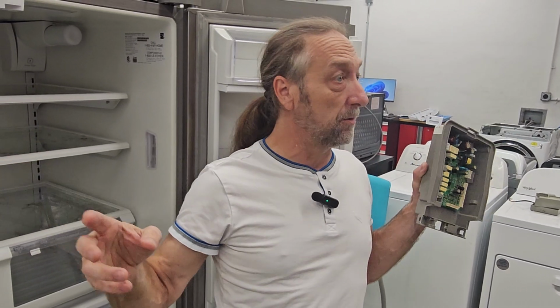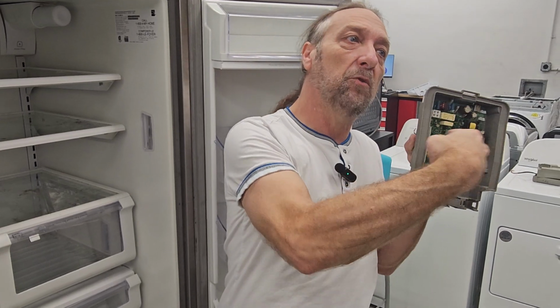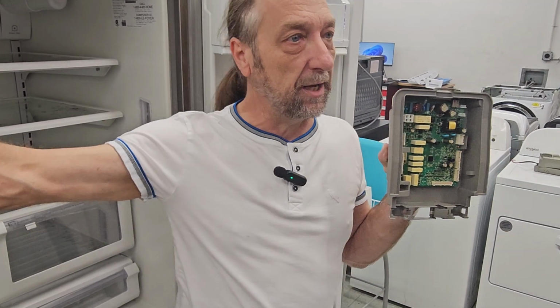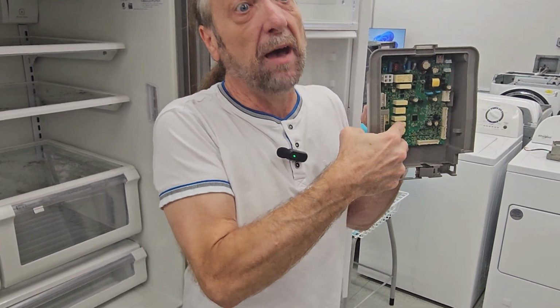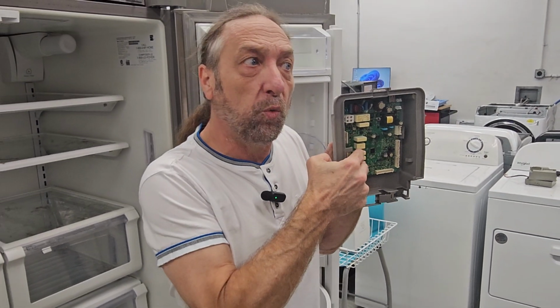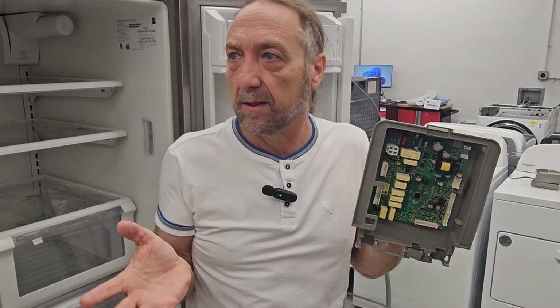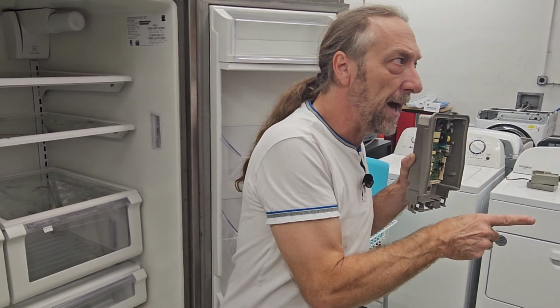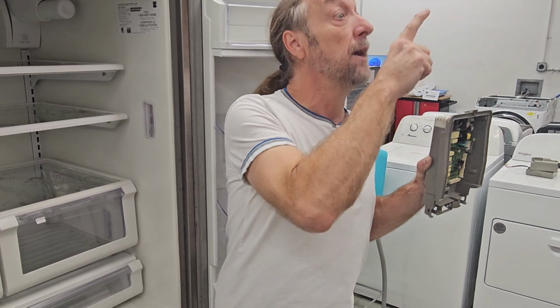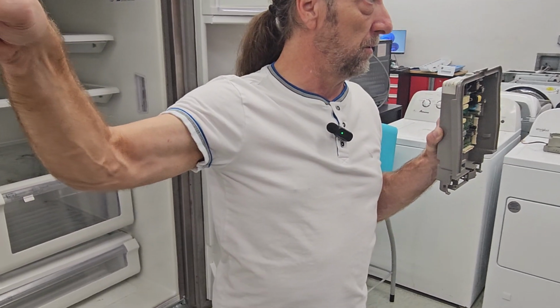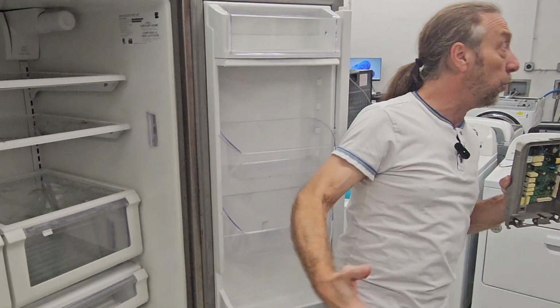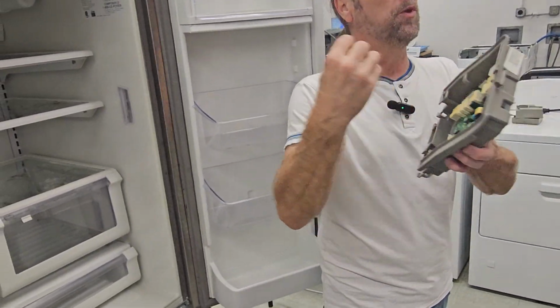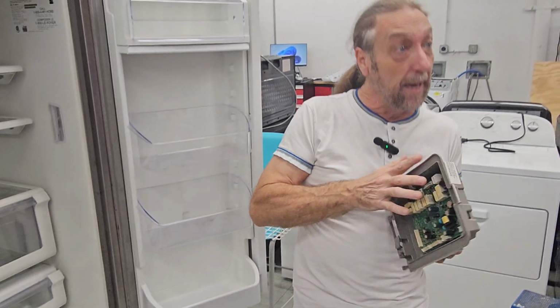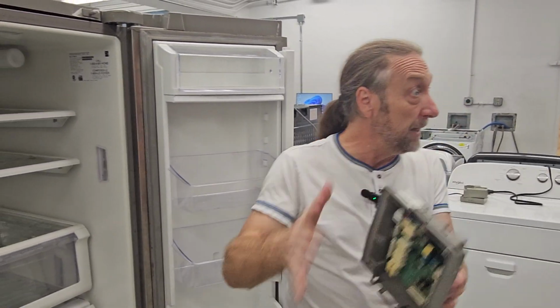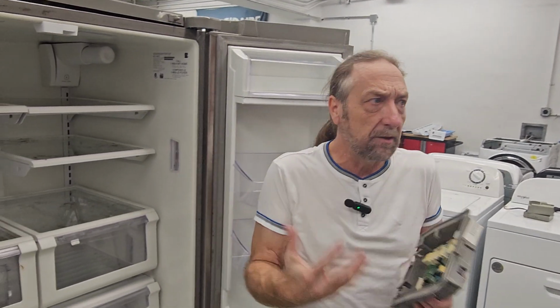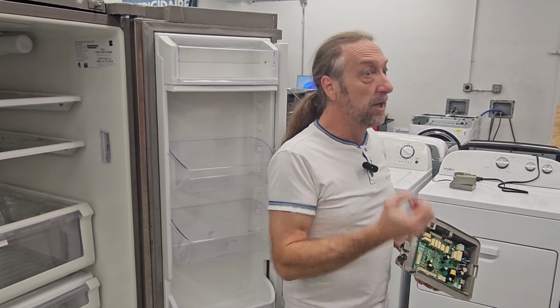I gave a hint. I could go plug it back in, and on those same two wires, check if I have 120 volts. If I have 120 on those same two wires, what does that mean? It doesn't mean the motor's bad, it means the control board's good because it's sending power. We still don't know if there's a broken wire or connection, so we don't assume the motor's bad, but we know the problem isn't the board. I've eliminated the board.